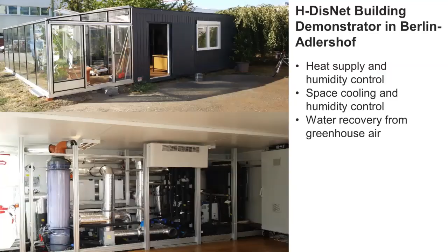Here you see two schemes: the upper one shows the heating function, the lower one the cooling function. It's a basic explanation. In the middle is the heat pump we are using. You see my pointer, here are the absorbers - you saw the absorber from Switzerland, here we have a similar element. The most simple system circulates air from the building through the absorber, reducing humidity and converting latent heat into sensible heat. That can be interesting if you have humidity sources in the building.